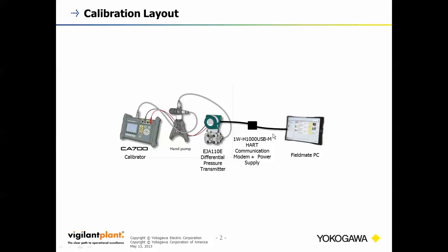And then we have an interface here, a HART modem and power supply that's powering the transmitter and then providing HART communication back to this PC that's running our Fieldmate software, which is our device configuration software that's going to help us facilitate this calibration and our device configuration.